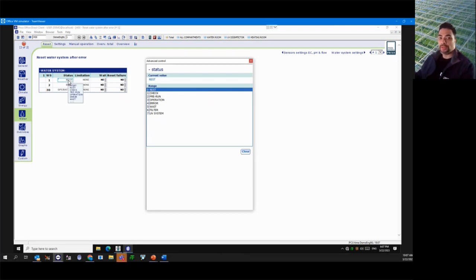So in the future, if you ever wanted to know what happened during the water system, like if it alarmed or something, if you're not storing the status, you're not going to have the data to go back and figure out, okay, at what times did we have some sort of error or something like that. So you can store these values, and if you graph them, it's just going to be a horizontal line, but it'll give you a number so you can see, okay, what was it, right? The most common ones are probably just an error or an operation. So 3 being operation, 4 meaning some error for some reason.